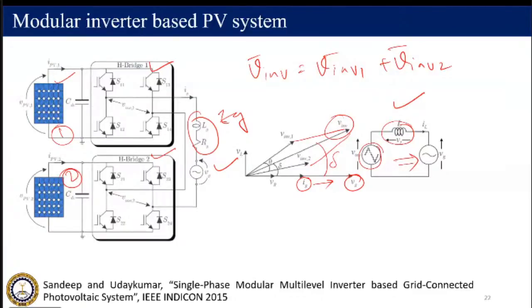Now what are the challenges here? PV module 1 should be extracting the maximum power out of it, and PV module 2 should also extract maximum power, but the H-bridges, bridge 1 and bridge 2, are connected in series, so in a way they are both coupled. The power out of PV1 and PV2 gets coupled, and then they get injected into the grid.